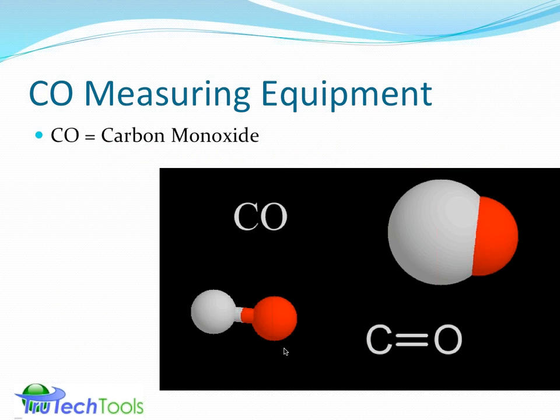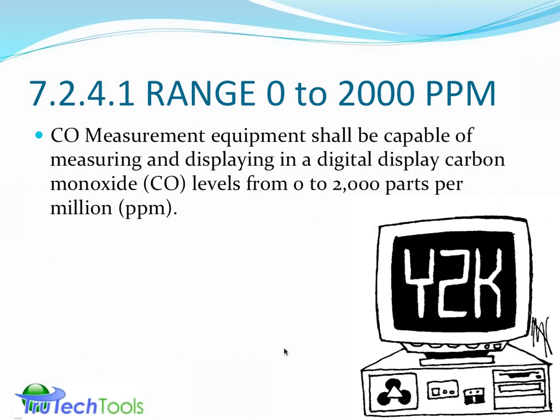The next standard category, or the category for diagnostics, is CO measuring equipment. We're talking about CO, carbon monoxide. That's what's shown on the screen there. One of the key specifications in 7.2.4.1 is that the range of the carbon monoxide meter needs to be 0 to 2,000 parts per million. So that's pretty simple, pretty straightforward, pretty easily met by pretty much all the equipment on the market that's used for flue gas testing.